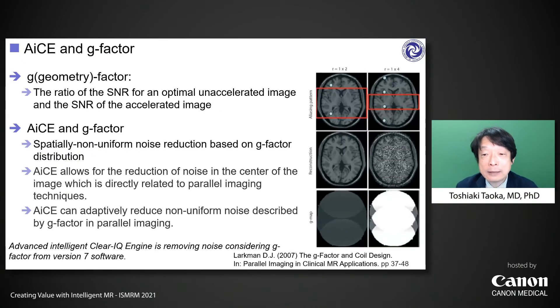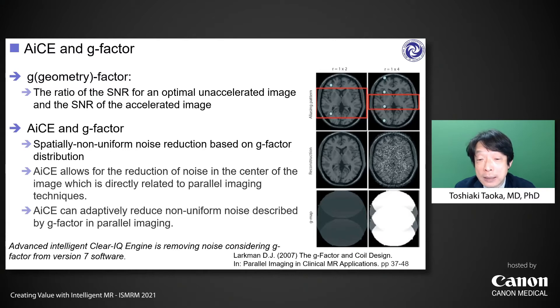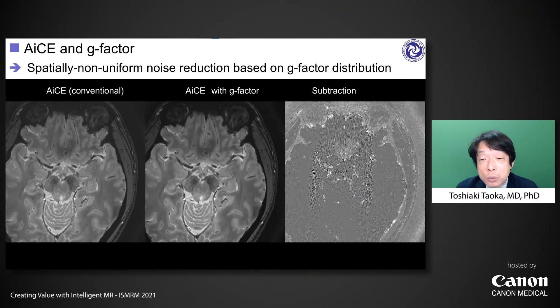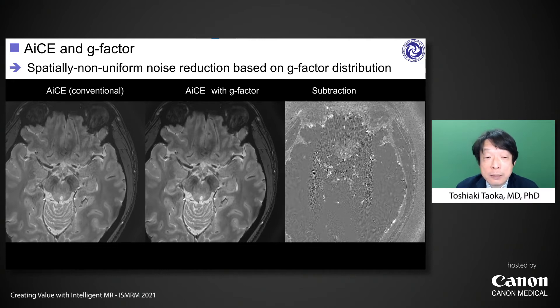AICE can make adjustments considering the g-factor in parallel imaging from version 7 software. The g-factor is a ratio of SNR for an unaccelerated image to that of the accelerated image. In AICE processing, non-uniform noise reduction based on g-factor distribution is performed. AICE can adaptively reduce non-uniform noise described by the g-factor in parallel imaging. By subtracting conventional AICE images from g-factor-considered AICE images, we can recognize the distribution of noise reduction, with stronger noise reduction in the deep part of the brain where SNR is insufficient in parallel imaging.